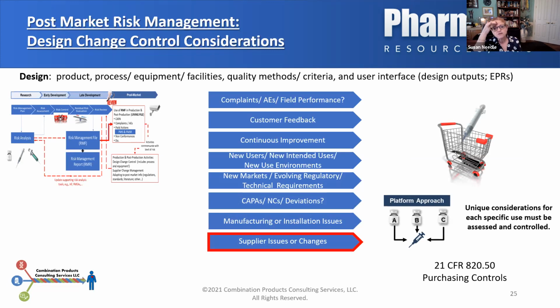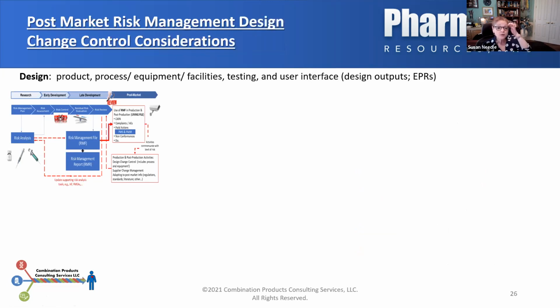And if you are using a platform device approach for your combination product, this becomes especially important, because under that platform approach, I might be using one type of device that I want to apply to multiple drug constituent parts to deliver them. And my job in risk management is to look at each one of those combination products and look at the unique considerations for each specific use and assess it and control it. So if I'm using my Botox for the wrinkles on my forehead versus I'm using epinephrine for anaphylaxis, obviously, if I'm using the same device for both, my unique considerations for each of those products are going to be dramatically different. So I need to take those into account, and I have to work appropriately with my supplier to address that for that constituent part and the combination product as a whole.